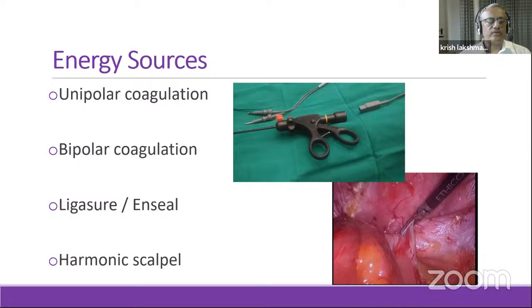So when you ligate a tissue, in addition to ligation, the instrument gives you an audible beep sound telling you the tissue is completely coagulated. That facility is not there in bipolar coagulation - it's a visual thing. You have to keep watching to see if it's coagulated. If it looks coagulated to you, it's fine.